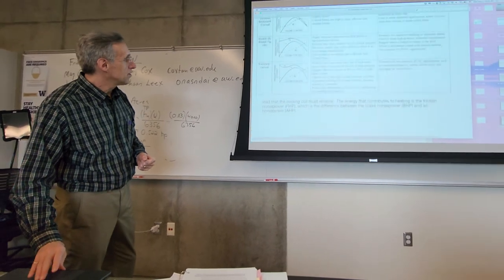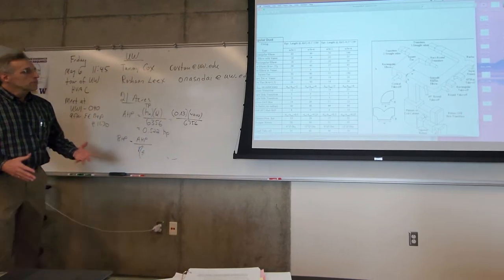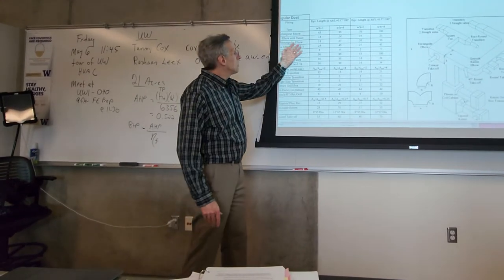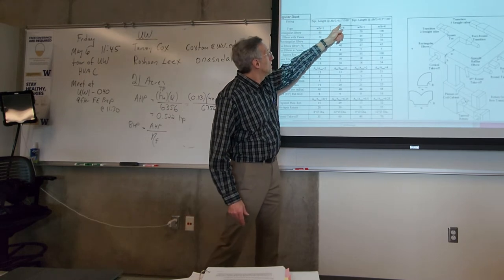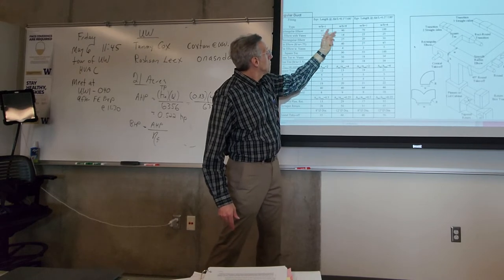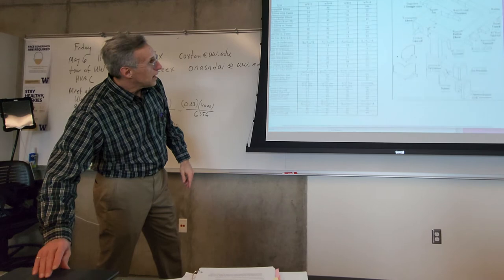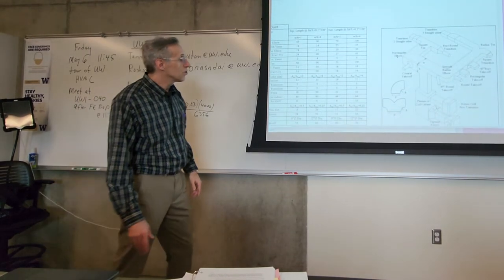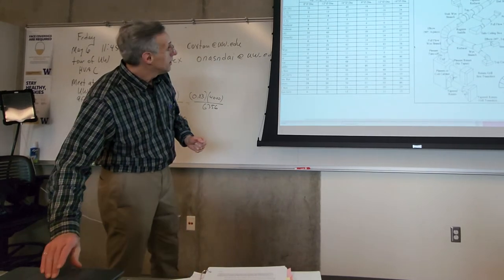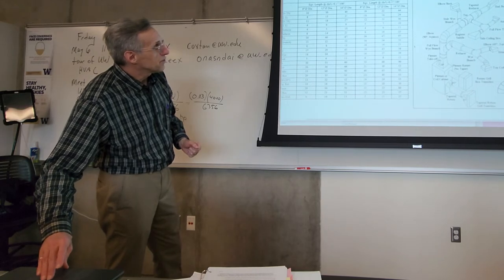So there you go, fans, air distribution. And then my little duct guy, this is not very good. I put this up as a reference for duct equivalent lengths, but these only apply under restricted conditions. If you have 0.1 inches of water per 100 feet or 0.3, and the diameter, kind of limited here, but it shows you what these fittings look like. This is for a rectangular duct and then for circular ducts here. And you can see all the different kinds of fittings.